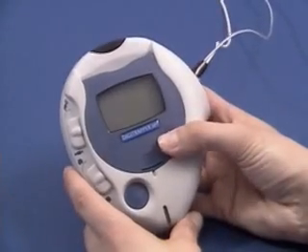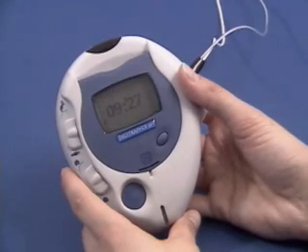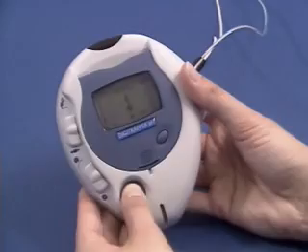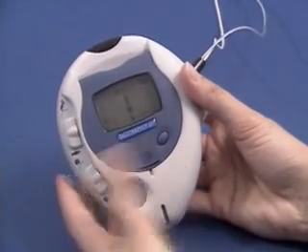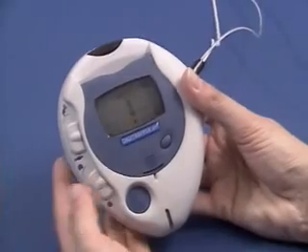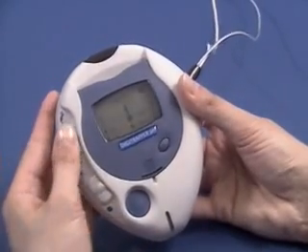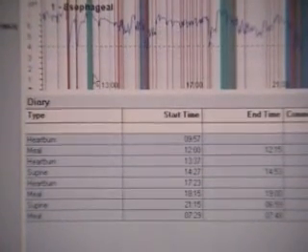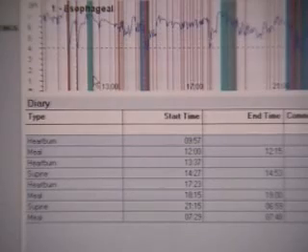Designed to make patient symptom reporting easy, the event button is used to indicate the onset of a symptom, for example, heartburn. By providing visual feedback, the period switches help the patient to reliably indicate both the onset and end of meal and recumbent periods. Electronic diary information entered through the use of the period and event buttons is captured along with pH study data.